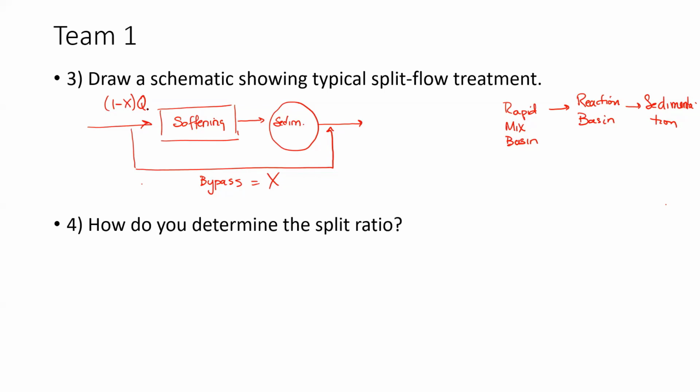Now, in processing or softening the water, the pH is going to range somewhere between about 10.5 and 11.3. We can't distribute water having that high of a pH, so we do one of two things. When we mix, it may be that the bypass is sufficient to reduce the pH when we mix the waters, or we may need recarbonation.